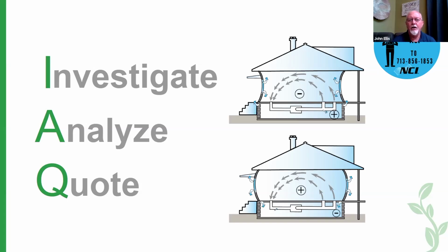Depending on your climate and what part of the country, the why doesn't change, just the how. In certain parts of the country, like California and some of the milder climates, we can offer a fresh air duct. Just a quick snapshot, that's a duct connected to outside through the system, connected to the HVAC. When it runs, it brings in a certain amount of fresh air. Also, in some of the drier climates, we can offer an HRV to bring in the air. What that does is temper it from outside by changing the temperatures. That will also add fresh air for dilution and will control our building pressures that way.